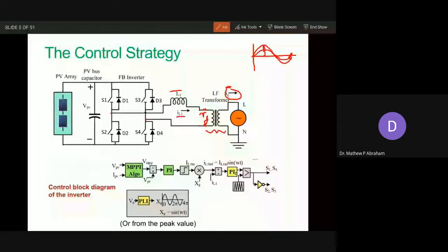So what we do is we keep on adjusting Ig, the grid current injected, depending upon the maximum power point. The theory of maximum power point injection is known to you. You will be getting a power wave shape like this. So we will always keep the inverter operated at the maximum point. So we decide the voltage at which the power is to be injected by measuring the PV voltage.